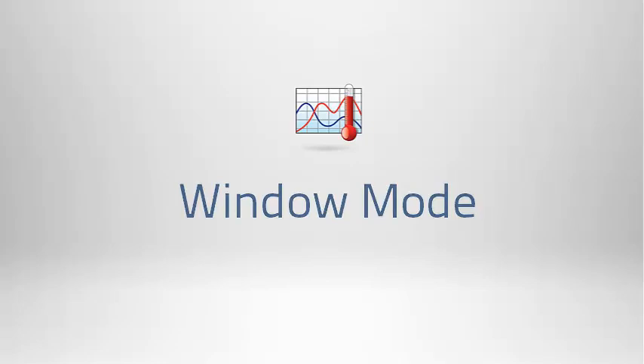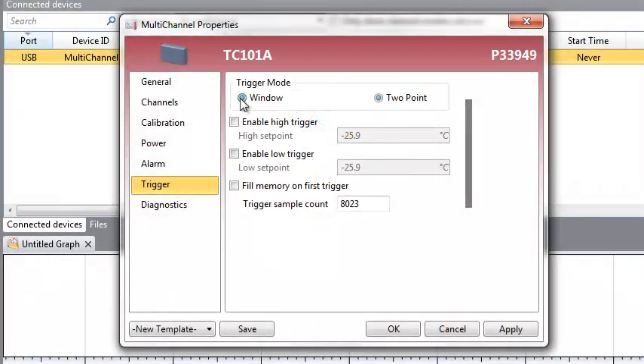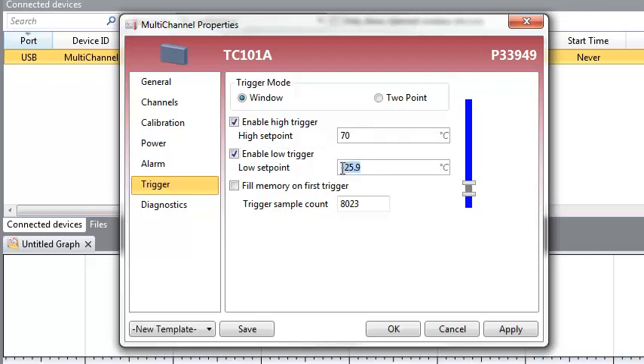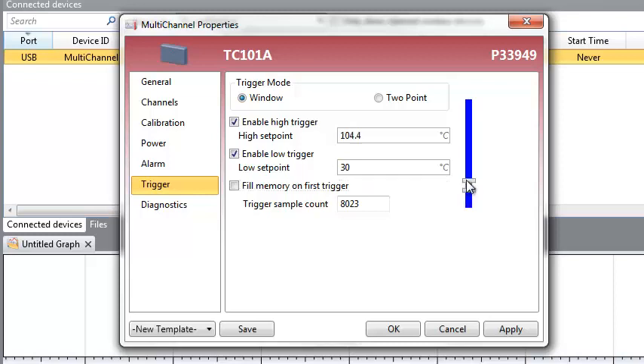First, we will review Window Mode. Start off by selecting the Window Mode radio button. Click the checkbox to enable the high and low set points and enter your desired settings in the fields provided. For this example, we will be using a high set point of 70 degrees Celsius and a low set point of 30 degrees Celsius. The high and low set points can also be changed using the sliders on the right.